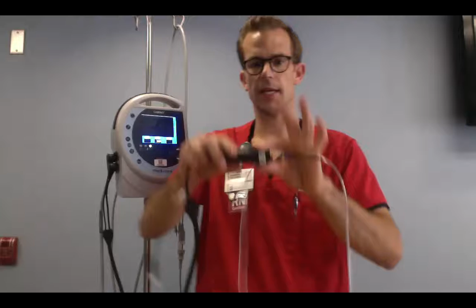So if you're transferring a patient to CT scan, all you will do is unplug this from the patient, secure this to the patient, ensuring that it doesn't come out, and then send the patient to CT. When you come back, all you'll do is plug it in. There's no zeroing involved. You'll never zero it again. If anyone's telling you to re-zero it, do not listen to them. You can't re-zero it. I mean, you can, but it will basically make the ICP monitoring null and void.